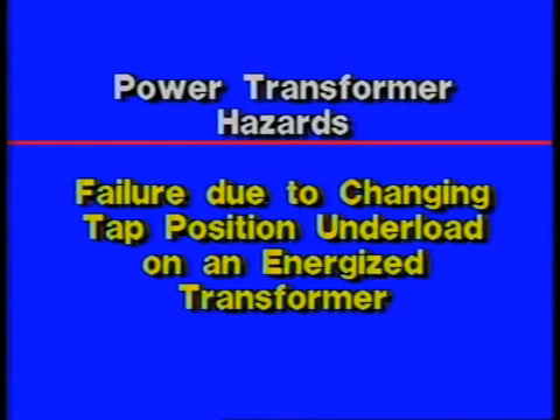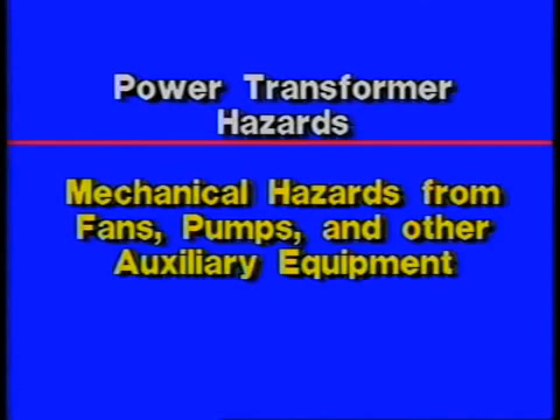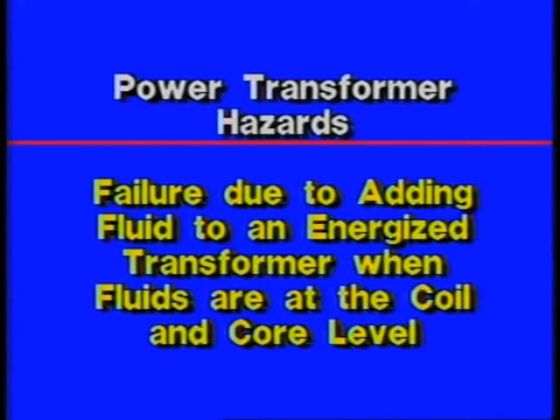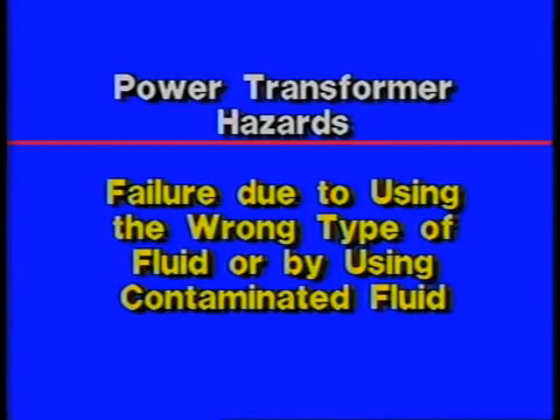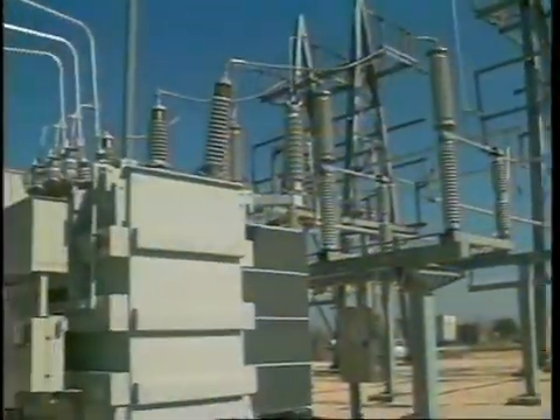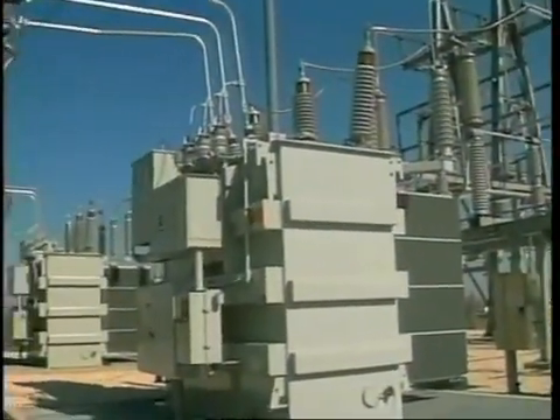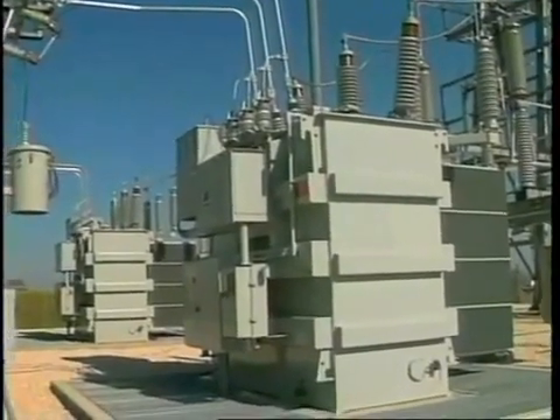due to changing tap position under load on an energized transformer, mechanical hazards from fans, pumps, and other auxiliary equipment, failure due to adding fluid to an energized transformer when fluids are at the coil and core level, and finally, failure due to using the wrong type of fluid or by using contaminated fluid. So as you can easily see, work with power transformers can be hazardous if proper safety precautions are not followed.